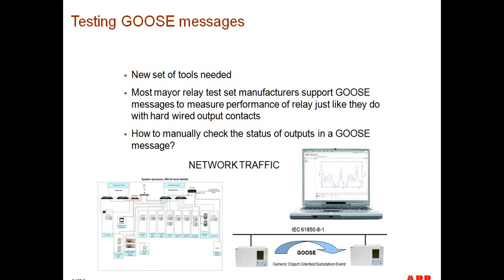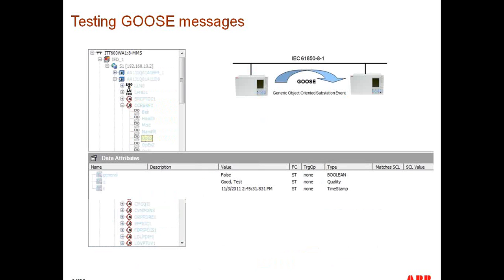Now, how do you get an understanding of the system when a test set is not available? How do you measure continuity on a GOOSE message? Well, the way that's done is by using troubleshooting tools or IEC 61850 testing tools. There are a few available that can provide field engineering with immediate feedback as to what is the value of certain conditions. In this case, I'm showing what is the value of my breaker fail function. We could see that I am looking at this device, circuit breaker fail function operation, and then I could see whether that is on or off, and then I could see whether that particular function is in test mode or not, which in this particular case it is.